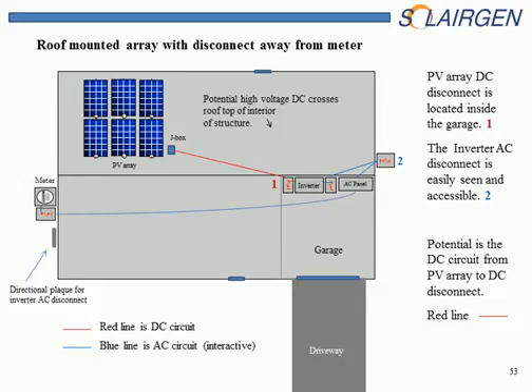If there's not a plaque, if they didn't provide additional information telling you where the inverter is, then you'll have to look for it. So in this case, with an older string inverter system with high voltage, you can shut down the AC, but the DC potential is still in there. It's in a conduit, but there is still potential inside the house from the PV array to wherever that disconnect is. So finding that disconnect would possibly be the next important thing to do.